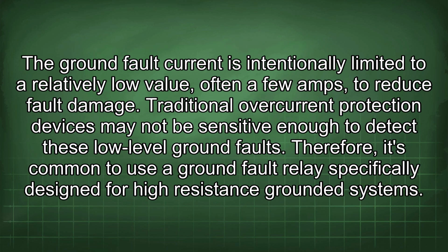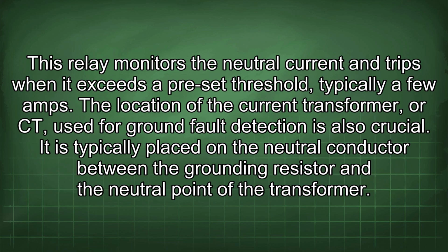The ground fault current is intentionally limited to a relatively low value, often a few amps, to reduce fault damage. Traditional overcurrent protection devices may not be sensitive enough to detect these low-level ground faults. Therefore, it's common to use a ground fault relay specifically designed for high-resistance grounded systems. This relay monitors the neutral current and trips when it exceeds a preset threshold, typically a few amps.